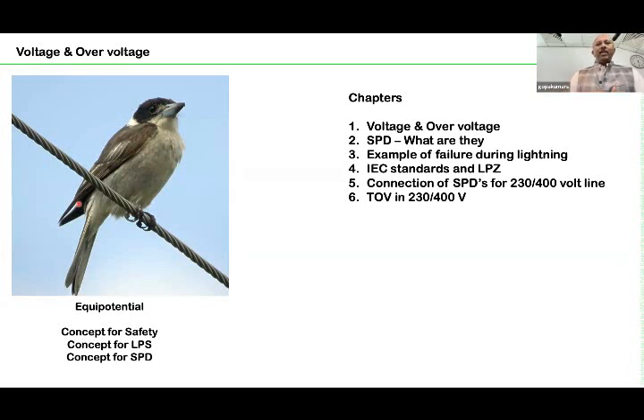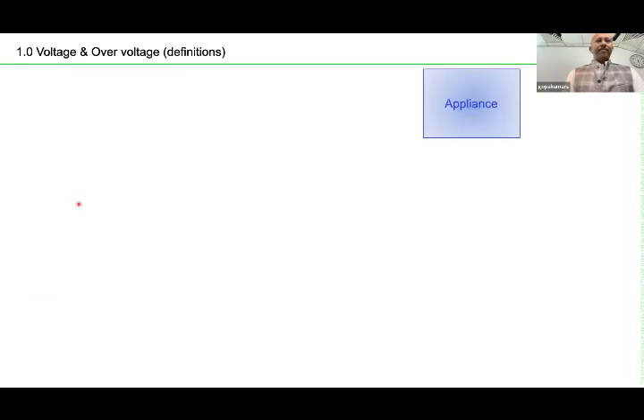So SPD protects against any kind of conducted surges. Conducted surges means some transient overvoltage is passing through a metallic conductor. The SPD will create an equipotential bonding, so that the conducted surges do not destroy the equipment. That is the important point. So you should keep this in mind. Because, for example, SPM, surge protective measure, consists of shielding, bonding, cable routing, and so on. Those subjects become very critical in a highly electronic environment, for example, defense, or some kind of research institutes. And nowadays we use electronics everywhere. So it becomes important everywhere.